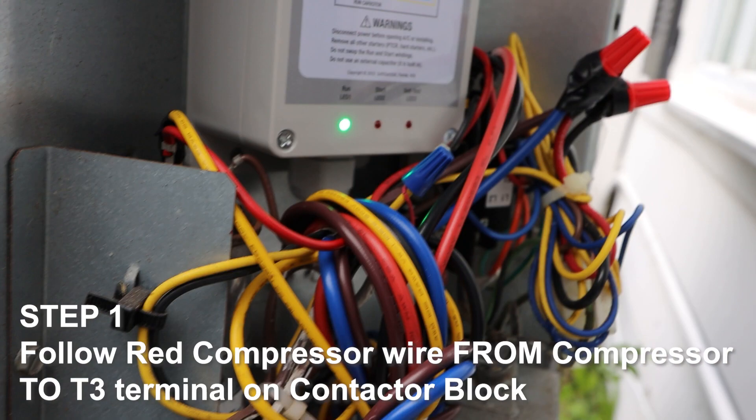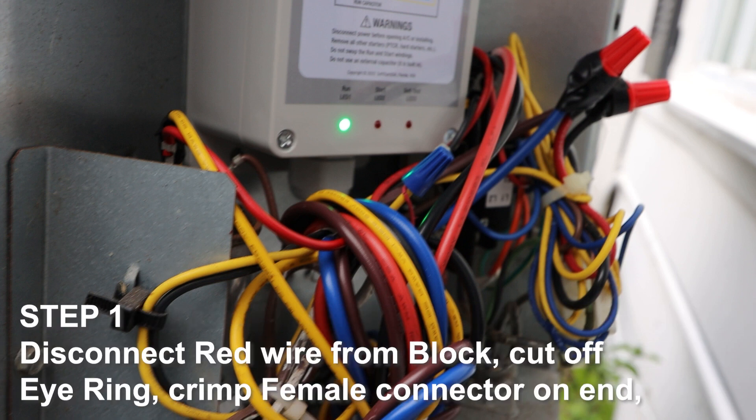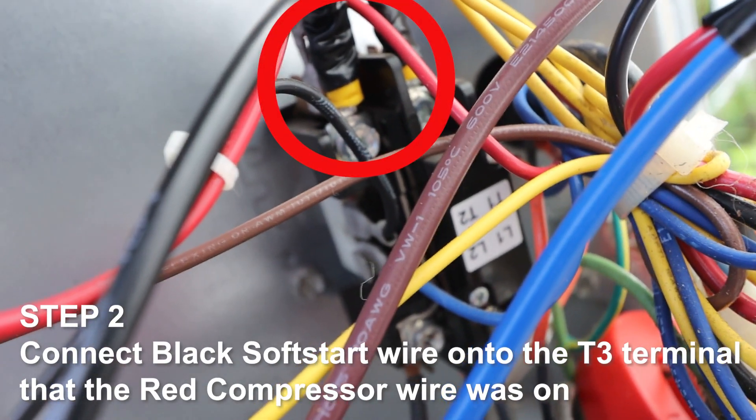Step 1. Follow the red compressor wire from the compressor to the T3 terminal on the contactor block. Disconnect the red wire from the block. Cut off the eye ring, crimp a female connector on the end, and connect it to the blue soft start wire. Tape the connection.